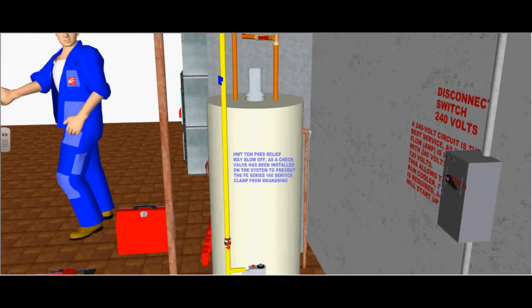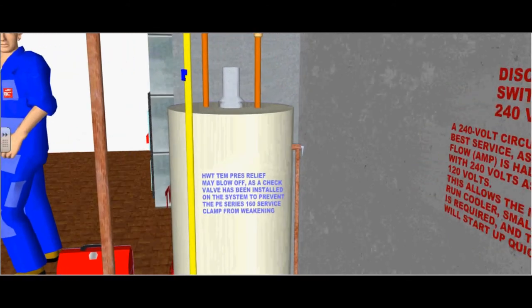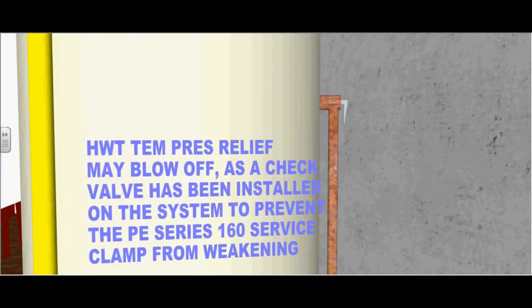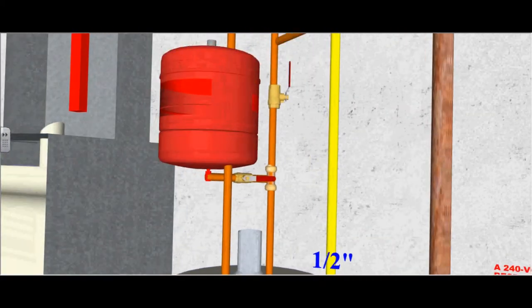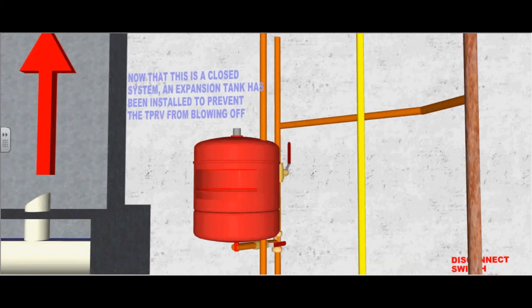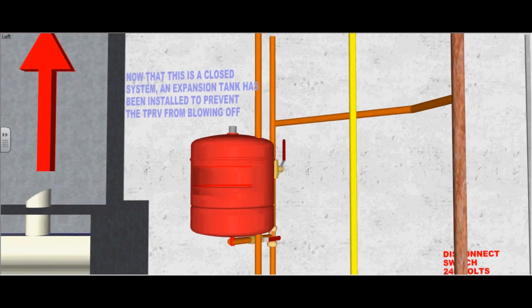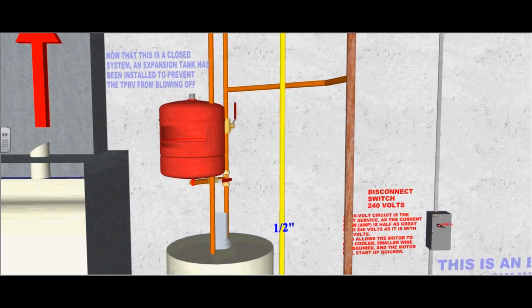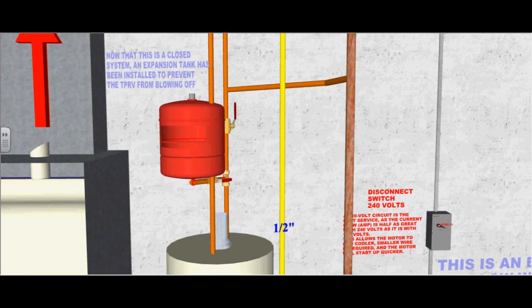In this particular case, the hot water tank temperature pressure relief valve may blow off, as a check valve has been installed in the system to prevent the polyethylene service clamp from weakening. In this case, now that it is a closed system, an expansion tank has been installed to prevent the temperature pressure relief valve from blowing off.